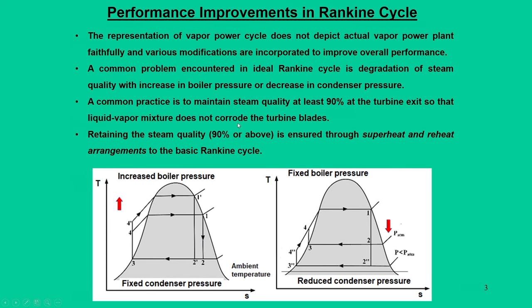First of all, when you deal with an ideal Rankine cycle, we say that saturated steam at state 1 expands in the turbine. During this expansion process, we land off at the exit of the turbine with steam quality not adequate with respect to operating requirements for the turbine. Turbine blades are designed to operate with steam in vapor state, but if the quality of the steam is not adequate, it normally erodes the turbine blades.